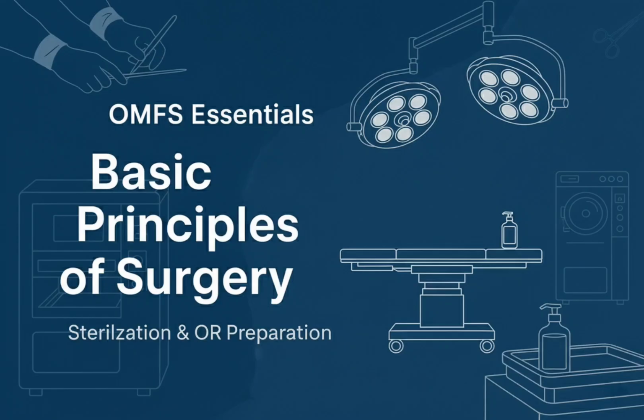Indications: surgical instruments, gauze, cotton, linen, gloves, and autoclavable handpieces. Contraindications: powders, oils, grease, and thermolabile materials like fiber optic cables or micromotor cords. Advantages: it is simple, economical, and highly reliable. Disadvantages: it tends to corrode instruments and dulls sharp edges.